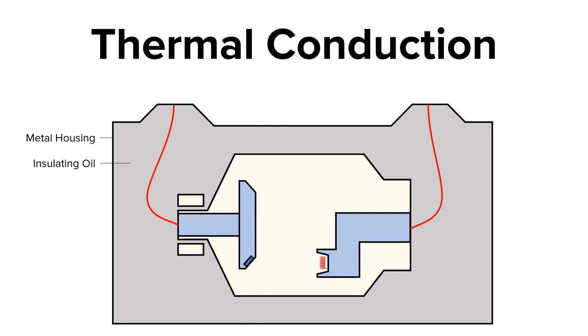Thermal conduction moves heat through direct contact. For example, heat from the anode target can travel through the anode neck, into the rotor, and out through the stator.